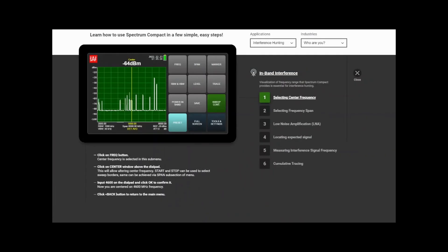For our first test, I want to show you in-band interference — a very classic test. In the applications menu, select interference hunting. You'll see four different interference scenarios available: co-channel, in-band interference, out-of-band interference, and wide-band interference. I picked in-band interference because it shows off the beauty of using a spectrum analyzer — something not easily done if you work with multimeters daily. That's where seeing the whole spectrum really comes into play.